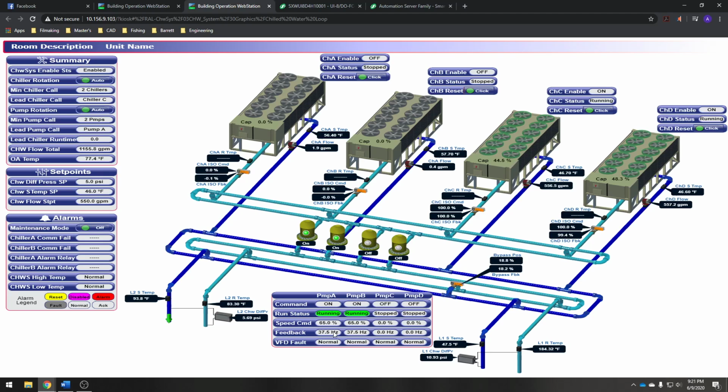And now that it overshot, it's backing off a little bit, going back to 60, 65. Since we're still up, the system's telling it, hey, back down to 64. That's actually really cool that we got to see that while we're sitting here. That's what the system's constantly doing. It's going to modulate these pumps to maintain this differential pressure.